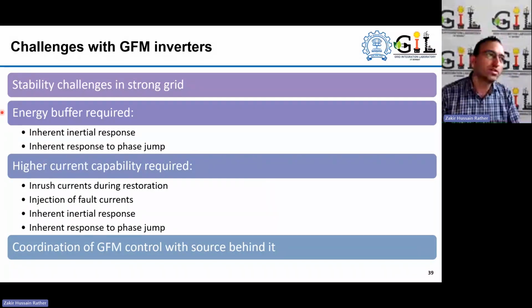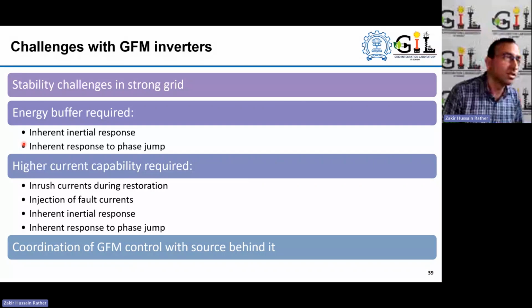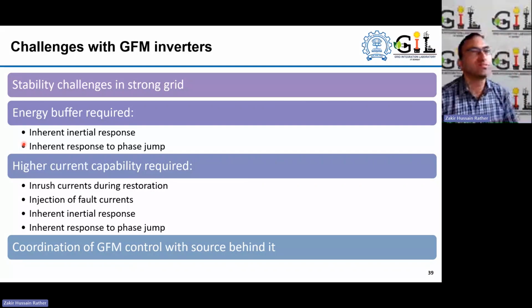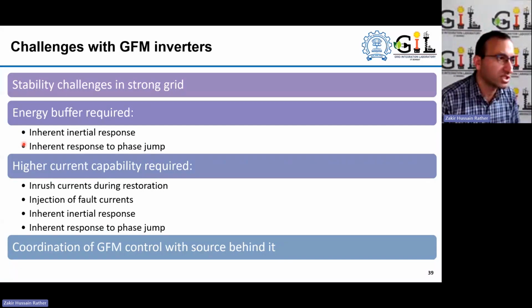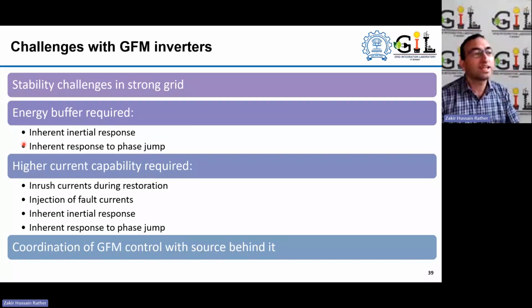An energy buffer is, of course, required here if you need to provide inertial response, and for sure if you need to provide black start capabilities. So that is an additional hardware and infrastructure requirement. Higher current capability is required because there are inrush currents that immediately flow into the system.